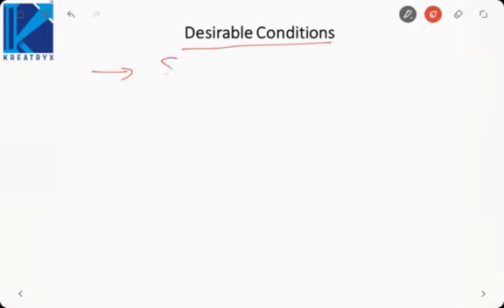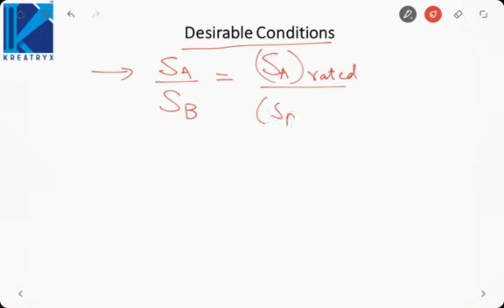The first is the load sharing, that is SA by SB must be proportional to their rating. Which means the transformer which has a higher rating must take more load as compared to the transformer with a lower rating. Why? Because the transformer which has higher rating is more equipped to take on higher load. Its winding will be thicker so that it can handle a larger amount of current. So it is just like in general life, whichever is more capable should achieve more. So A has a higher rating, so A load must be higher than the B load. So we must say that the desirable condition is load sharing must be proportional to the kVA rating.